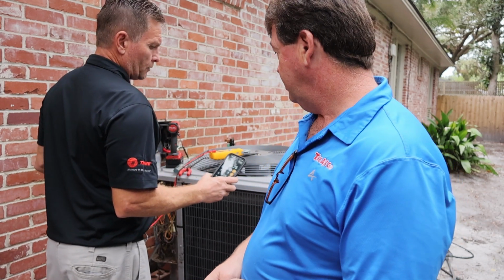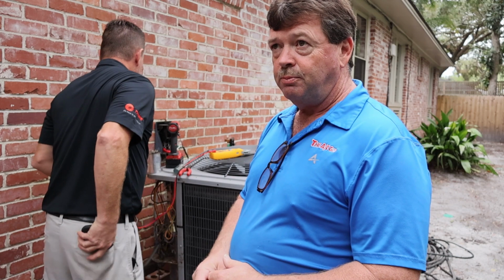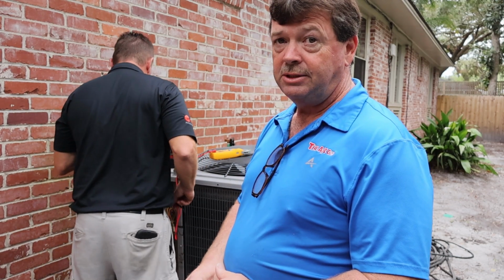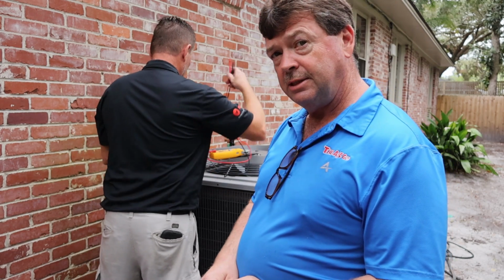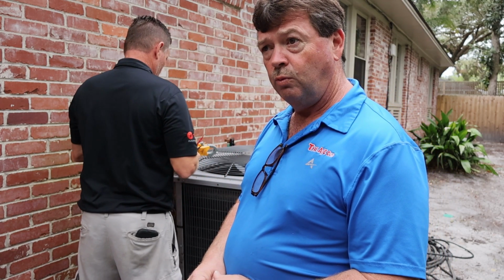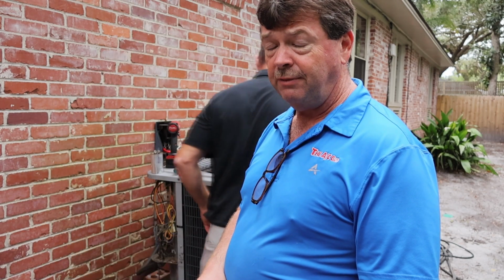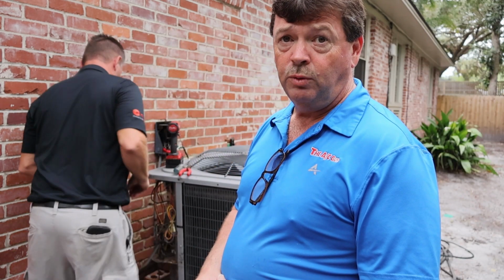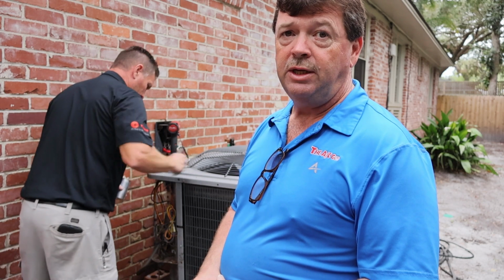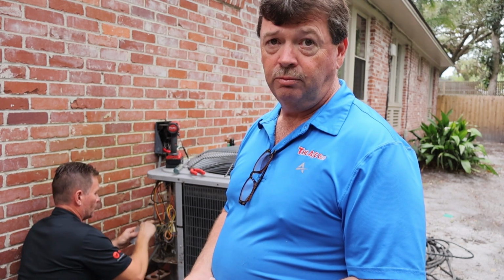And Dave said this is borderline. It's right on it, 42.75. So it's probably at the point where it needs to be replaced. So we're going to replace it, and we're also going to confirm warranty status because it could be under warranty. If this machine's over 10 years, no need to check warranty status. If it's not under warranty, the customer will have to pay the expense. If it is under warranty, they'll just send us one from the factory. Now we're going to get authorization from the customer to let them know what we're doing before we spend their money. So we'll let them know that the capacitor's weak and we advise replacement, and they can choose either way. But we've done our job.